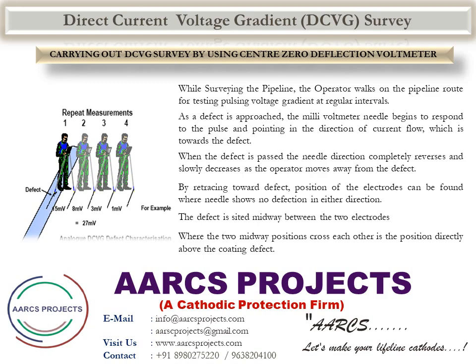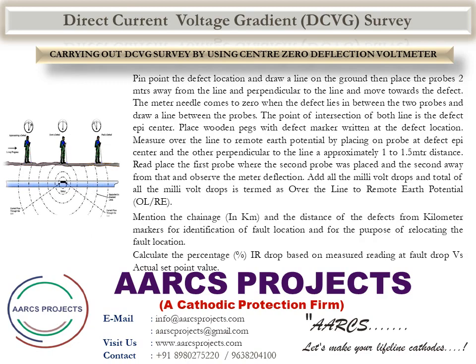By retracing toward the defect, the position of the electrodes can be found where the needle shows no deflection in either direction. The defect is sited midway between the two electrodes. Where the two midway positions cross each other is the position directly above the coating defect. Pinpoint the defect location and draw a line on the ground, then place the probes two meters away from the line and perpendicular to it, and move towards the defect. The meter needle comes to zero when the defect lies between the two probes — draw a line between the probes. The point of intersection of both lines is the defect epicenter.